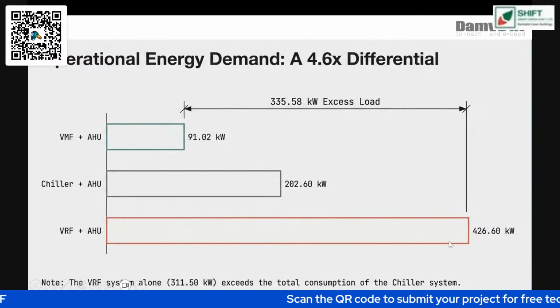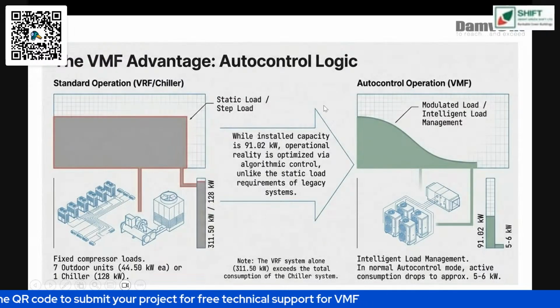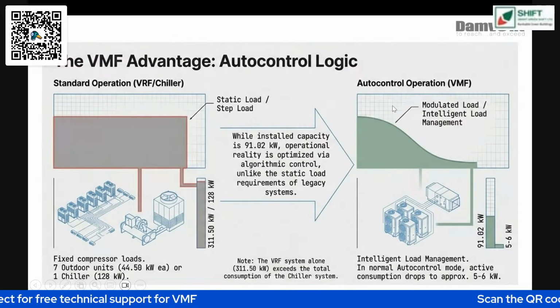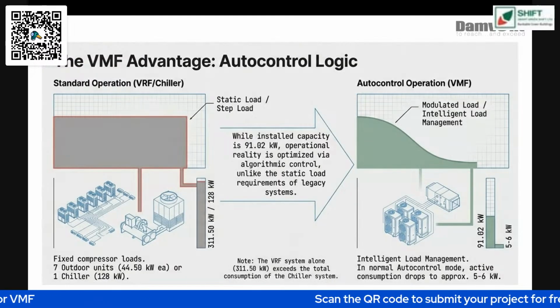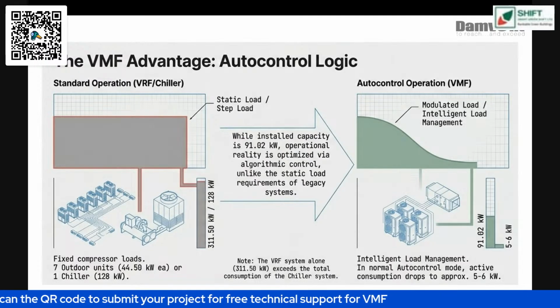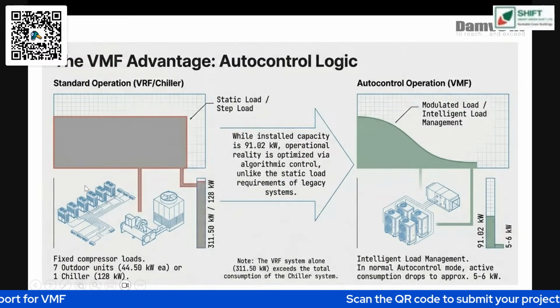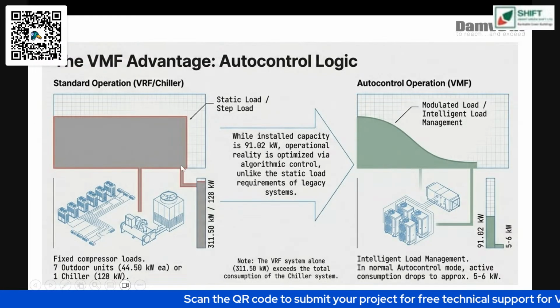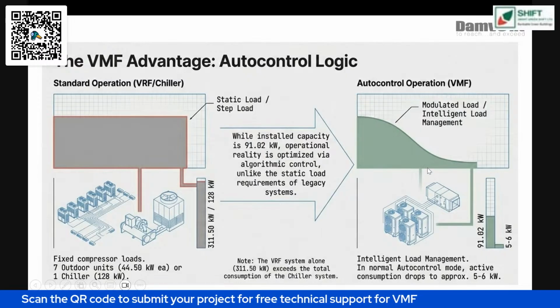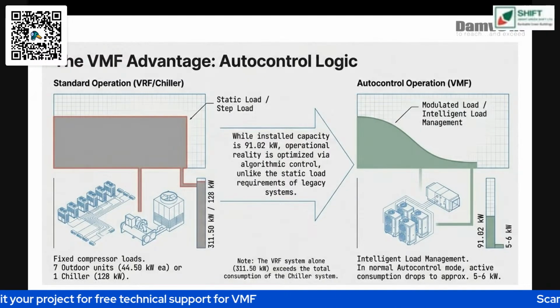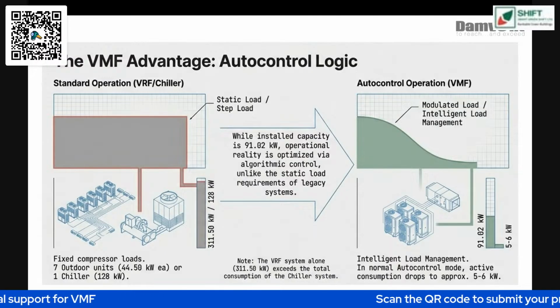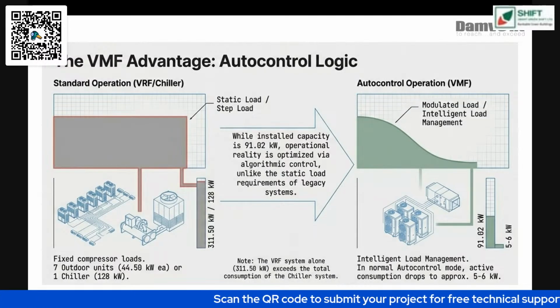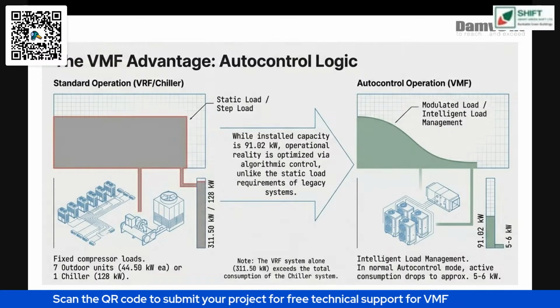So even double, both chiller and VMF show very low energy consumption compared to the conventional VRF system. It's really important. Additionally, we have a kind of auto control operation, because the VMF units are all integrated with a BMS system and intelligent load management, already integrated in the system. We also reduce energy consumption between 5 and 6 kilowatt compared to a static system. The demand is most of the time the huge energy consumption factor, so having variable load or variable consumption is much better, because it changes according to the demand and the load. That's the advantage these systems bring.